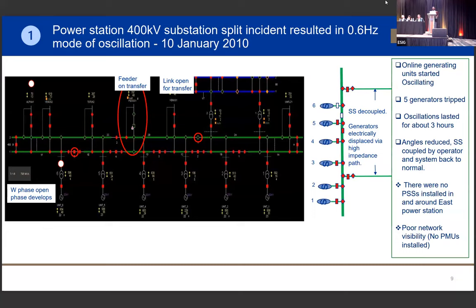Back in 2010, there was an incident that nearly caused a system blackout. It was early in the morning, around 4 o'clock, and a unit was coming back to synchronize from an outage. One feeder, the Pegasus feeder, was on bypass because they were working on the breaker, so we used bus coupler B on the left-hand side, on 400 kV, as a line feeder. There was a fault on one of the lines on the left-hand side, and the breaker on the line didn't trip. Then the bus section tripped together with unit 6. You can look at the diagram that I drew on the right-hand side. The station was decoupled, so we had 5 units electrically connected far away from the rest of the system. During that time, about 5 generators tripped.